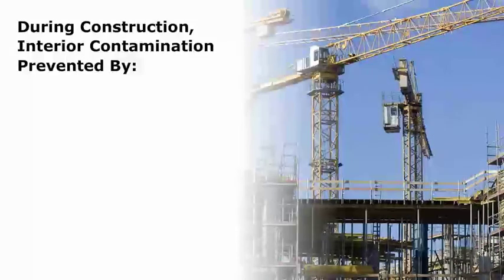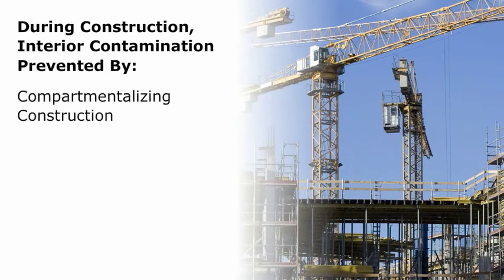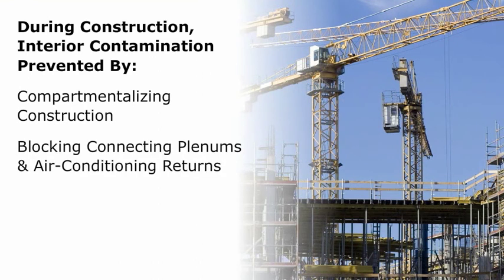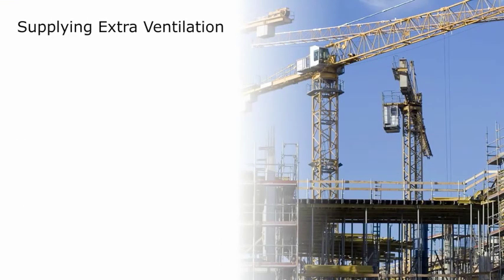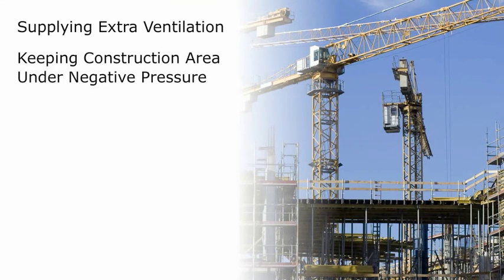During construction, interior contamination can be prevented by compartmentalizing construction with partitions and doors with closers, blocking connecting plenums and air conditioning returns, isolating work areas from occupied spaces, and supplying extra ventilation via window or door-mounted fans.